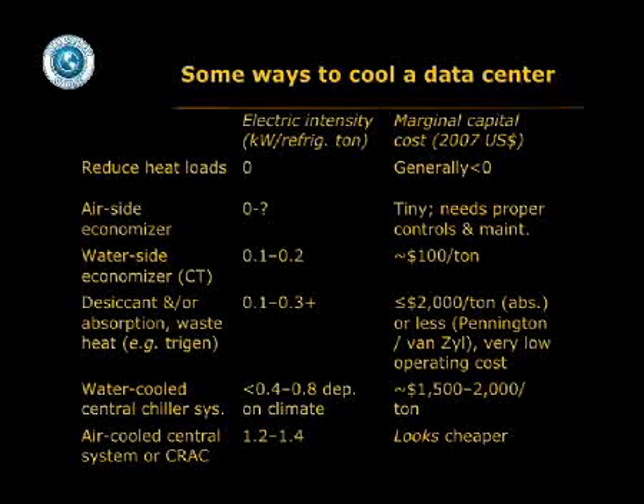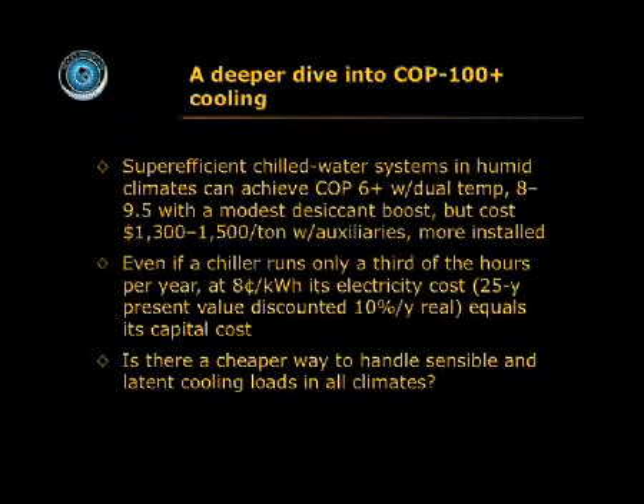And it looks cheaper, but not from a whole system perspective, and certainly not in OPEX. Let's do a little deeper dive into how we would get COPs upwards of 100. Of course, if you start with one of Mr. Lee's terrific COP 6+ systems, water-cooled centrifugal, you could boost that further by just putting a little desiccant on it to handle more latent load. It would cost what water systems cost.